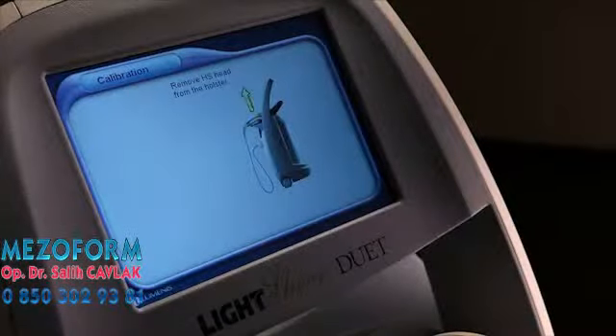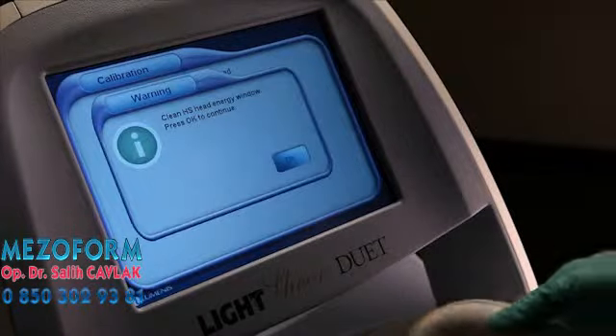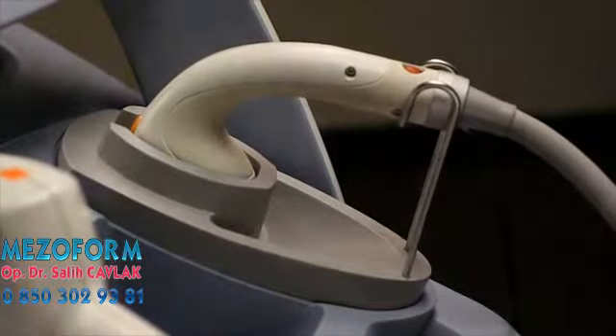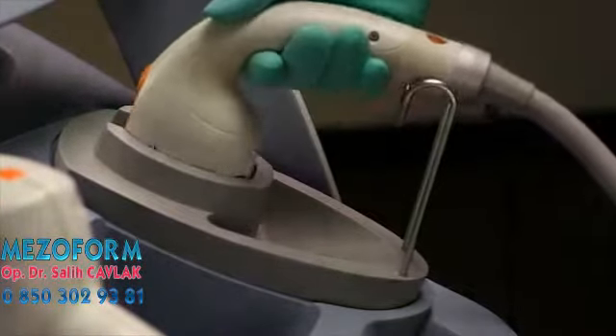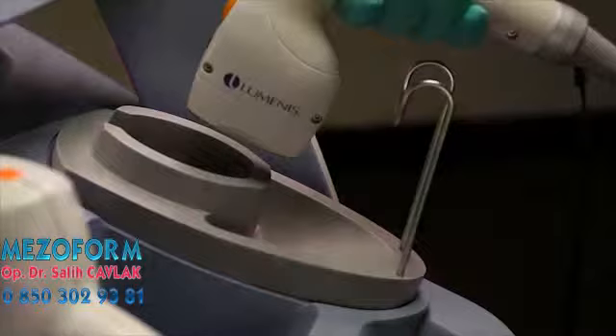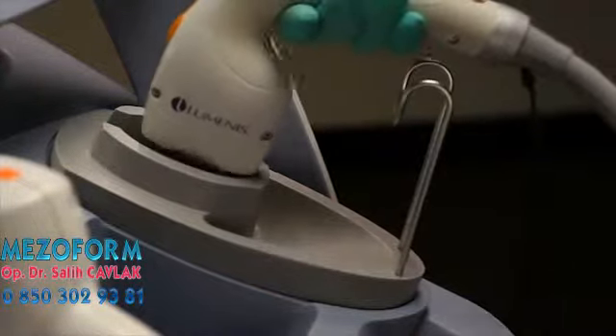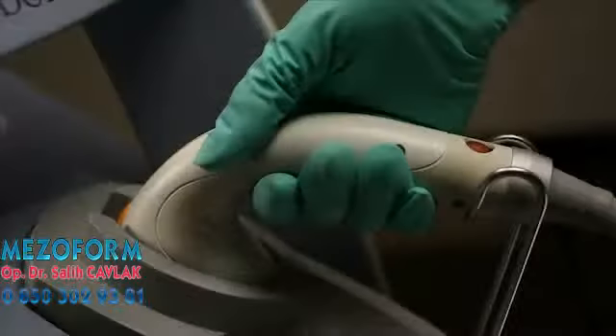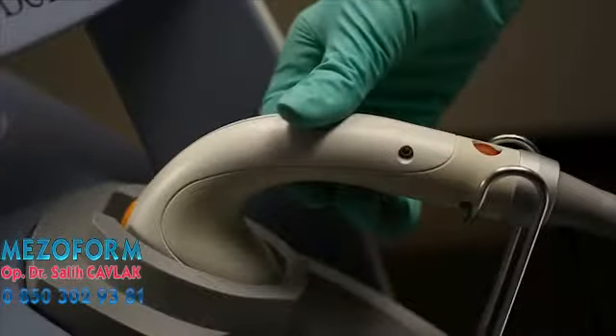Remove the handpiece from the holster and then carefully reinsert the handpiece into the holster. It is important to remove and insert the LightSheer HS handpiece perpendicular to the holster opening. This will avoid dislodging the holster itself. Ensure the LightSheer HS handpiece is properly seated prior to calibration so that the laser pulse is directed at the calibration window and not at an angle. This will improve the accuracy of calibration and avoid damage to the port.